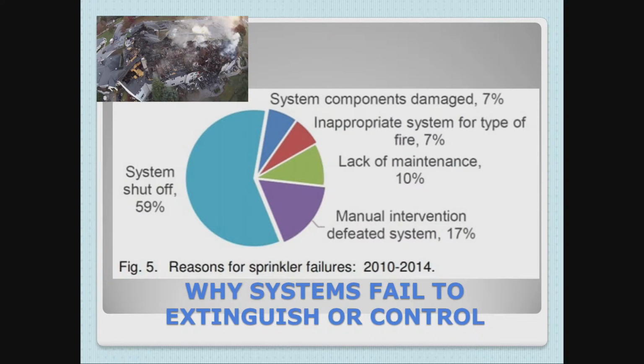The sprinkler system, it's about 99.9% sure the sprinkler system was turned off at the time of the fire. But the fire department connection was never used, and it wasn't in the best location. It met their code, but it was never used. And kind of what happened is they got there, they had a significant fire, and they focused on the life safety at the time, and maybe that was the way to go. But you got to figure if we could have eventually gotten that FDC charged before we had collapse, there's no way it's not going to make a difference. And certainly it's going to make a difference.